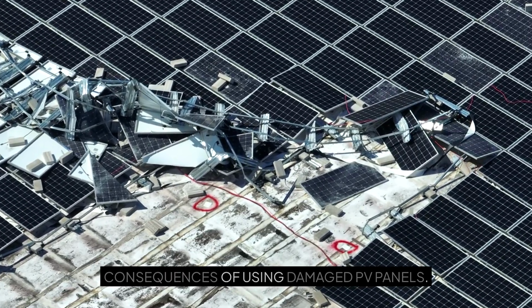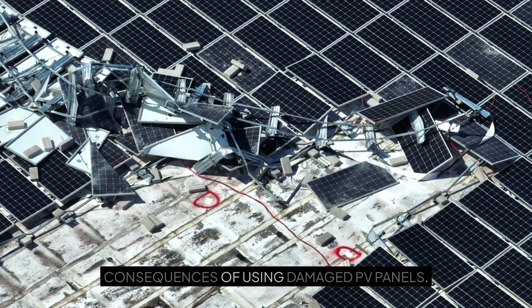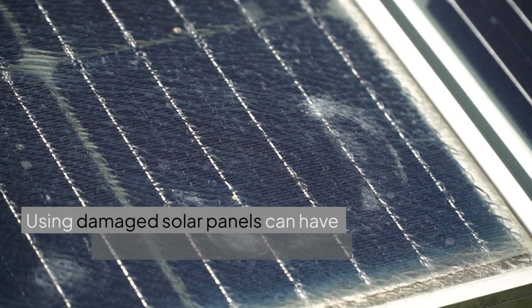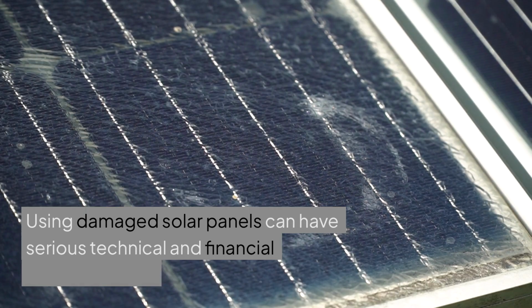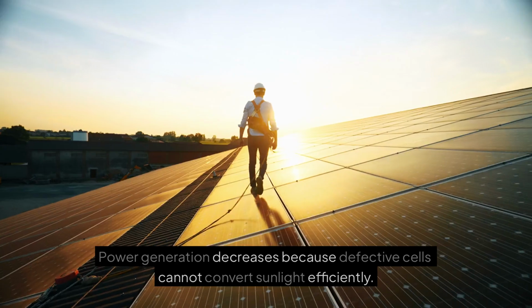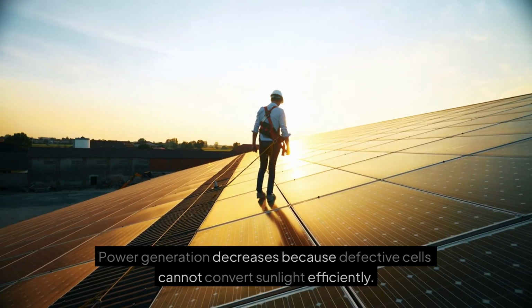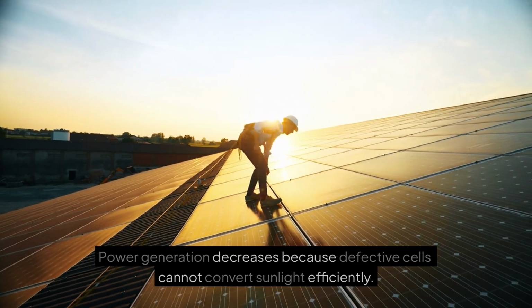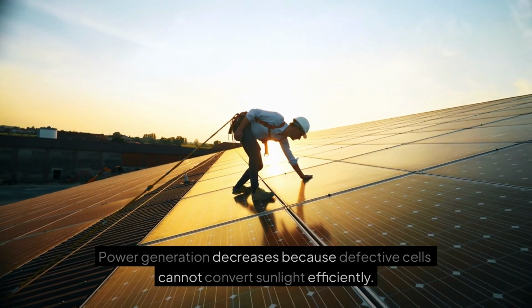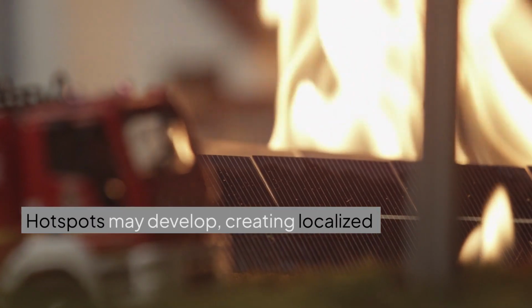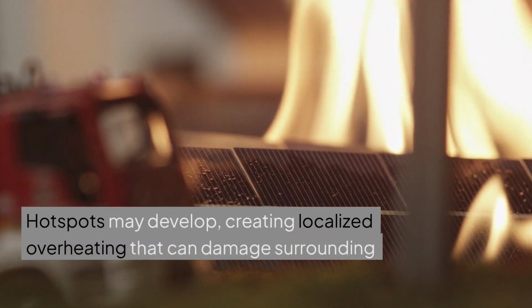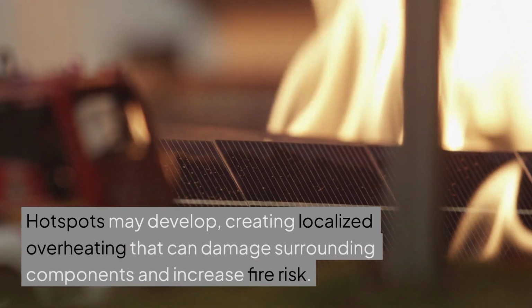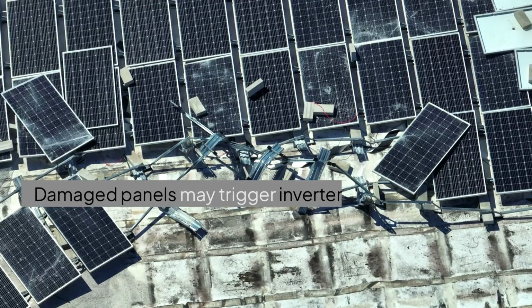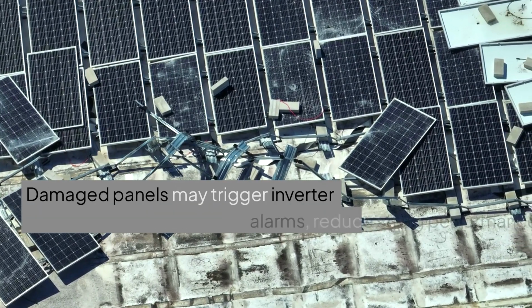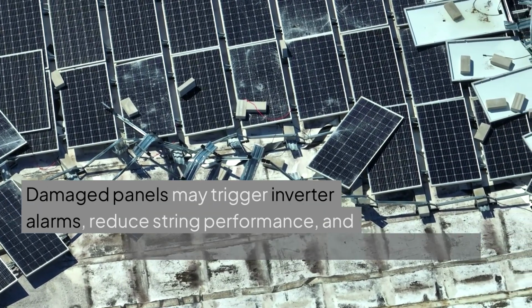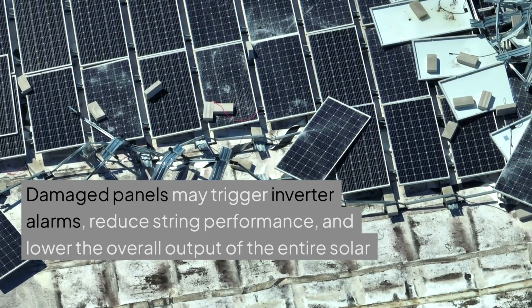Consequences of using damaged PV panels. Using damaged solar panels can have serious technical and financial consequences. Power generation decreases because defective cells cannot convert sunlight efficiently. Hotspots may develop, creating localized overheating that can damage surrounding components and increase fire risk. Damaged panels may trigger inverter alarms, reduce string performance, and lower the overall output of the entire solar array.